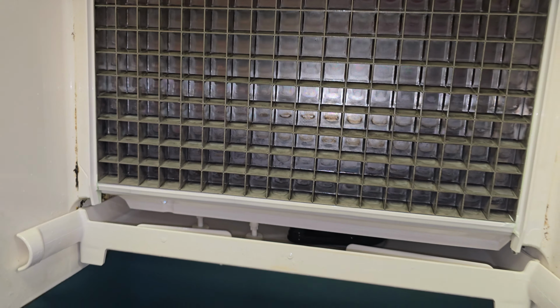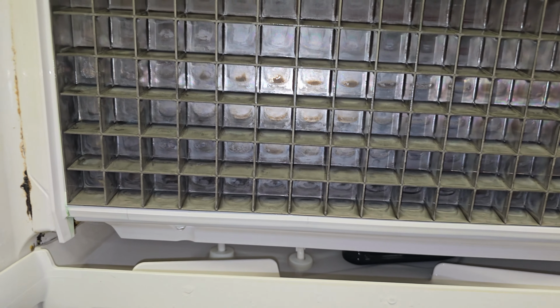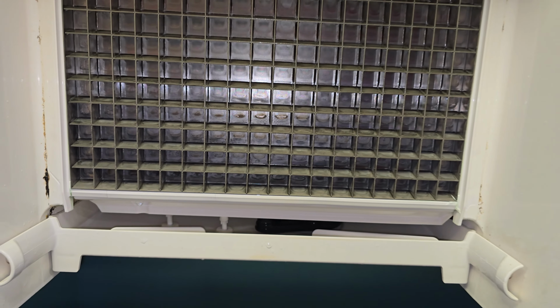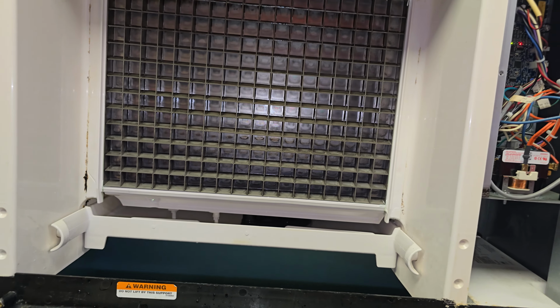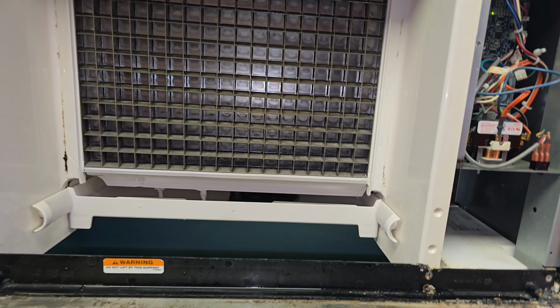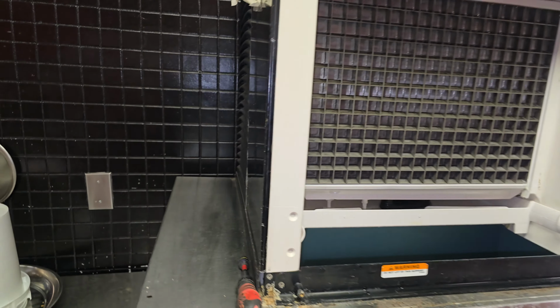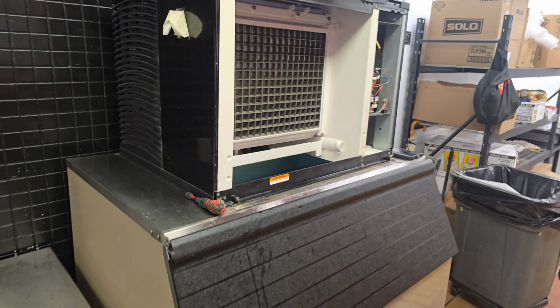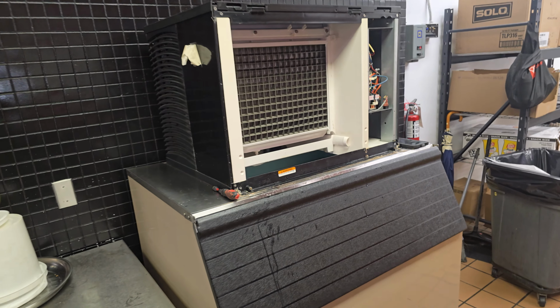If you take off this cover here, you can see both the ice thickness probe - that's the ice thickness probe. I'm going to have to clean it properly, the probe has to be cleaned properly, and I hope that will bring this machine back on. After this is done, if it brings the machine back on, good. If not, then we'll have to change both the ice thickness probe and the flow switch. That should bring this machine back on.